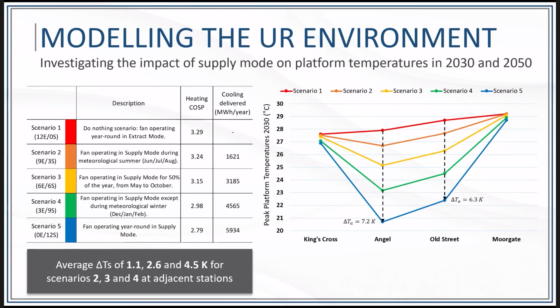Of course, this is if the system was running for the whole year in supply, and this might not be interesting from the perspective of the heat network operator, who wants to run the plant with the highest efficiency possible. But just to show you what this means, by running the system for the whole year in supply, this would provide nearly 6 gigawatt hours of cooling per year.